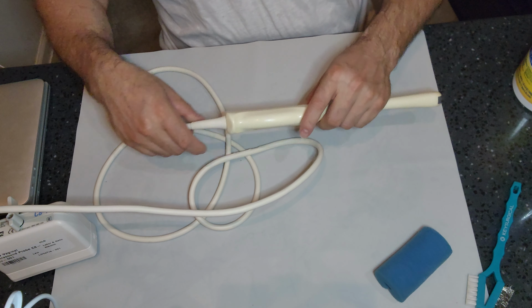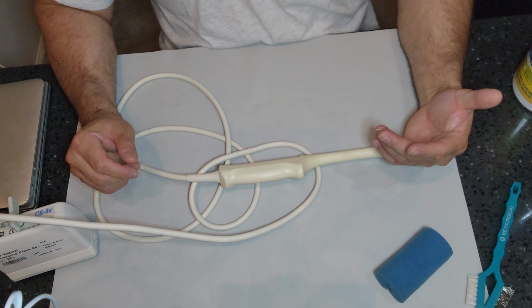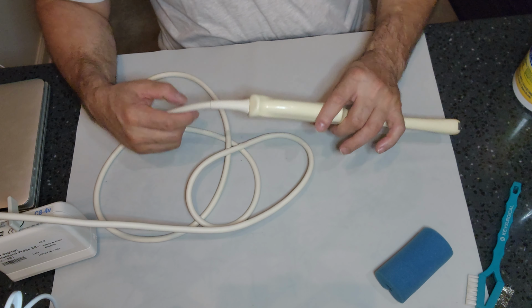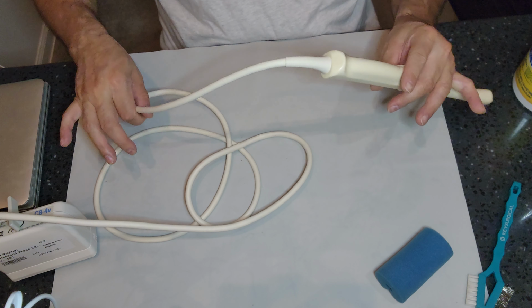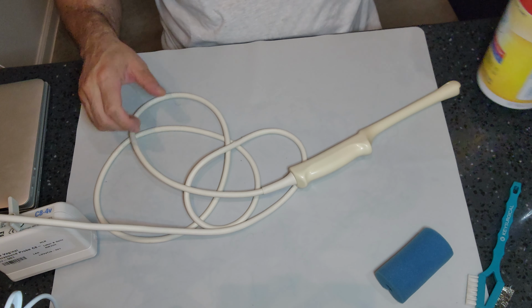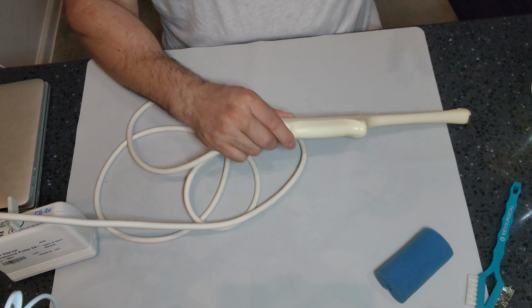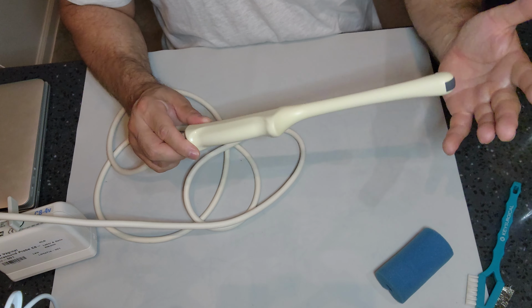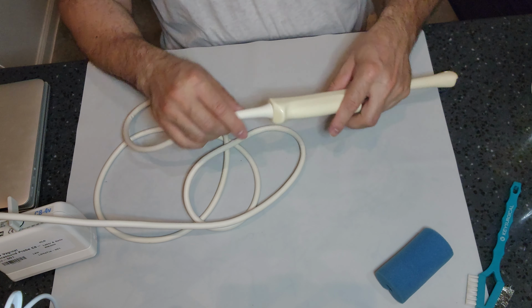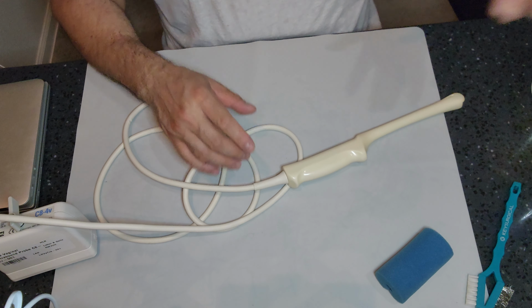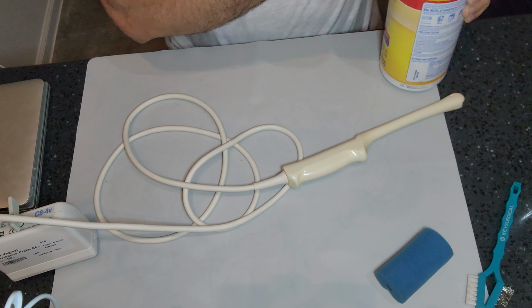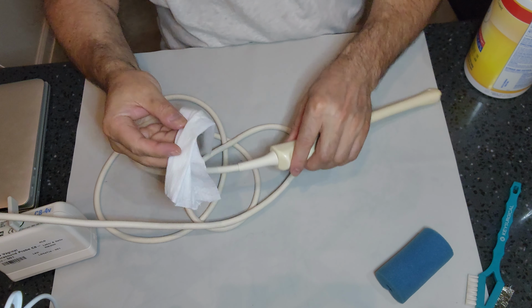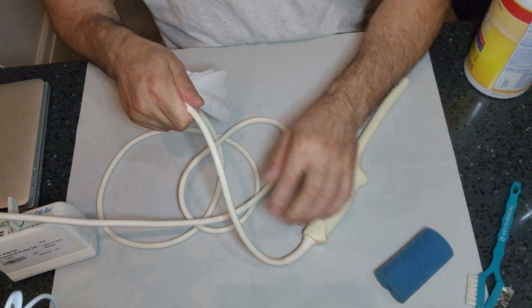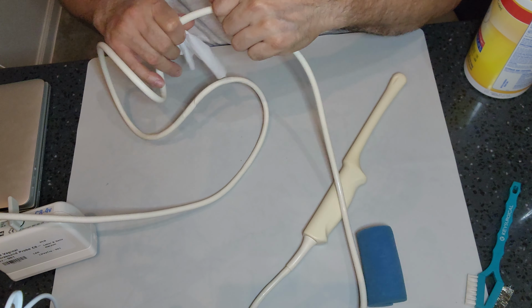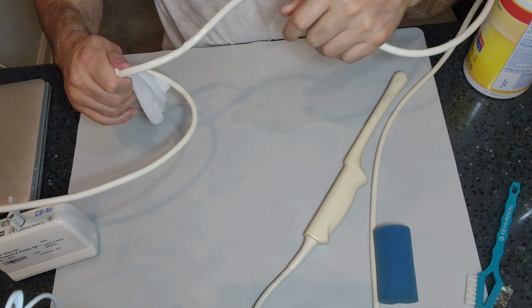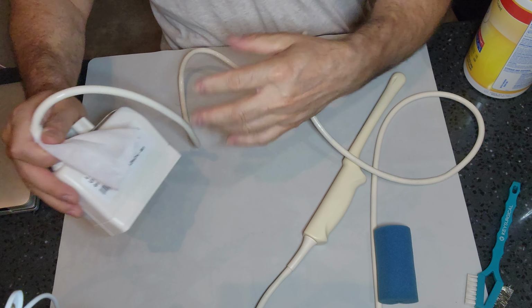So then the next step, what is it? So again, determine what the IFU states. The IFU may state that the actual cord can be low-level disinfected with a low-level disinfectant intermediate wipe, and the body needs to be high-level disinfected or sterilized. So you have to determine that. So if it's just a cord that gets low-level disinfectant, you want to go ahead and grab your wipe. Make sure your wipe is nice and saturated, and go ahead and wipe down your cord, making sure not to cross-contaminate or anything like that. All the way down to your connector.